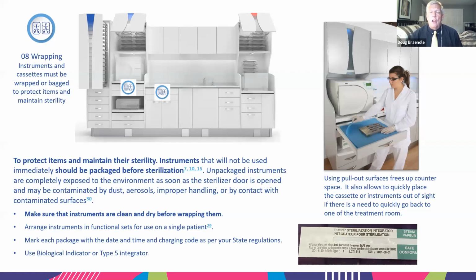And to Annie's point, you're still going to have to do a BI, but this doesn't take the place of a BI. So you're still going to have to do your BIs, but this will give you an indication each and every cycle, not relying on the machine itself to say, okay, good to go, and we're relying on the technology of the machine. This just gives you a positive yes or no at the end of the cycle, and you have 0 exposure. So I recommend doing that. Thank you, Amy. It's a reassurance. So good advice. Thanks, Doug.